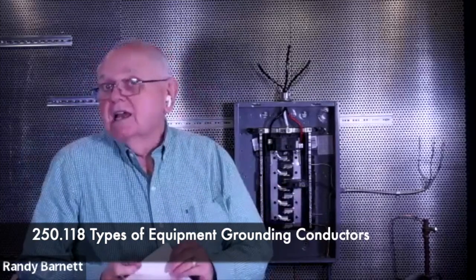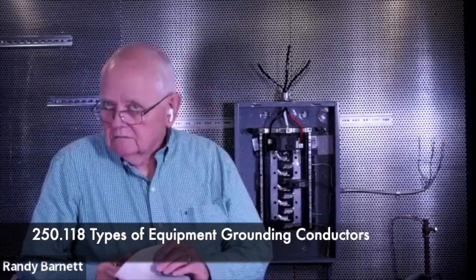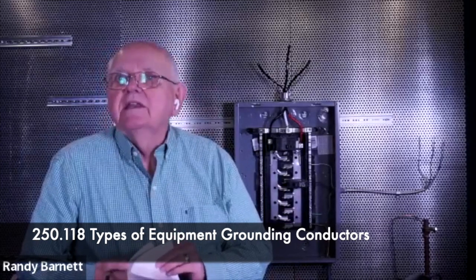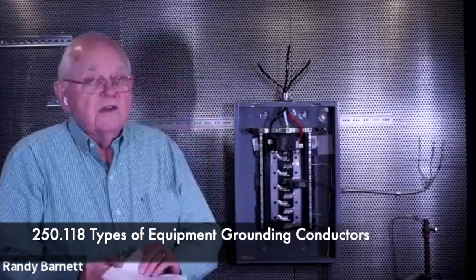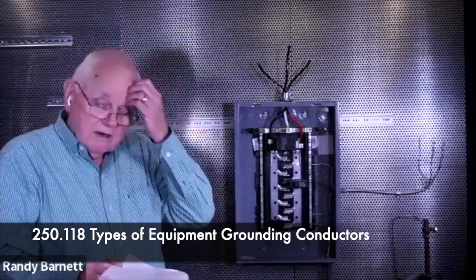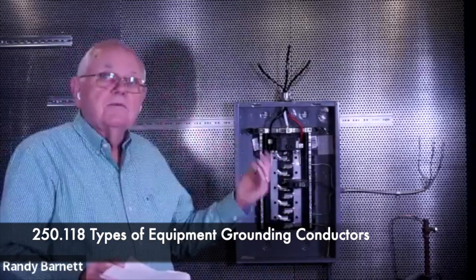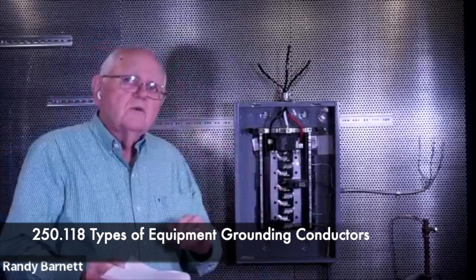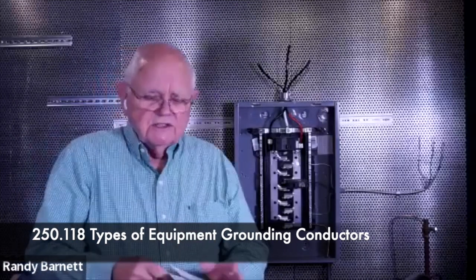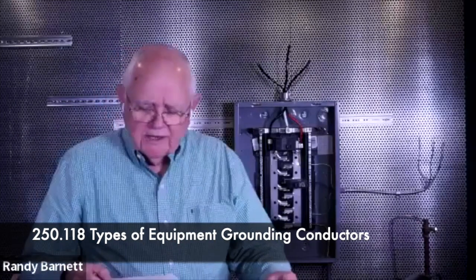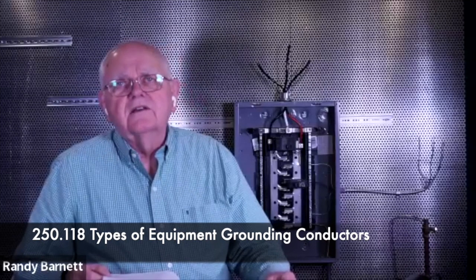Some other sections here. It doesn't have to have green insulation on it, does it? For instance, in type NM cable, not just Romex, right? But it's type NM cable in the code book. On the type NM cable, it's going to be bare copper. So we may have bare copper, green, or green with one or more yellow stripes on it. That's all covered. You see back here, 250.118 is types of equipment grounding conductors.